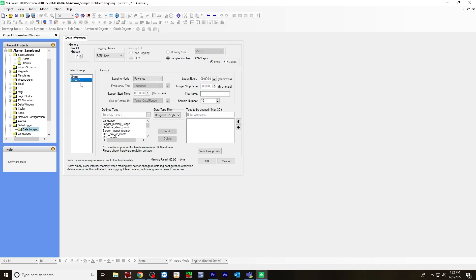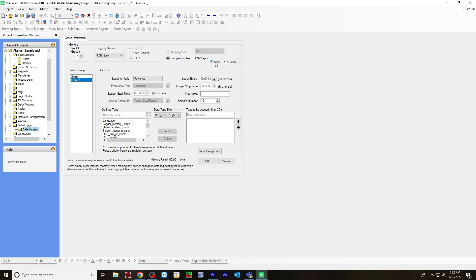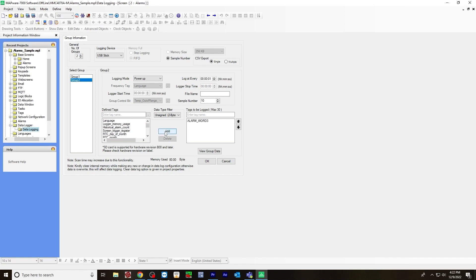This is going to be group two. Logging device, I'm going to use a USB stick. You can also do internal logging or use an SD card for the HMC 4070. CSV export will be a single file. You can also do multiple files. The logging mode will be on power up and it will log every one second. The tags that I want to log will be, for example, alarm word three.